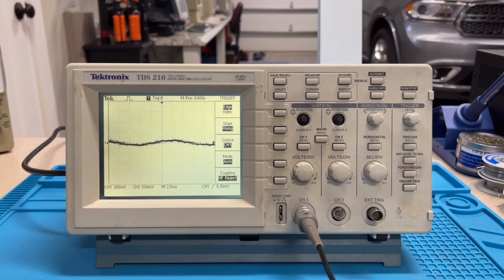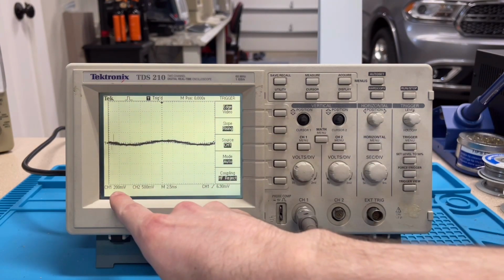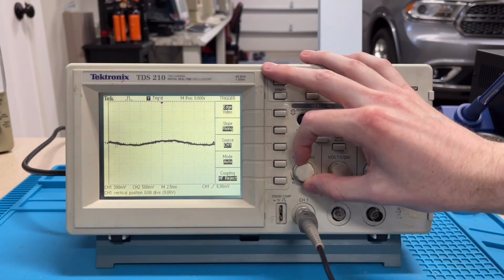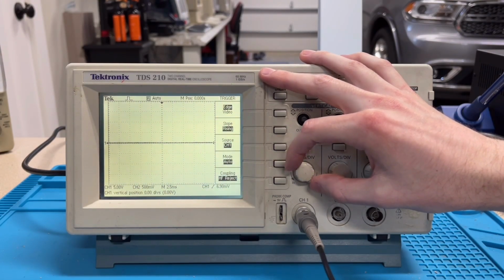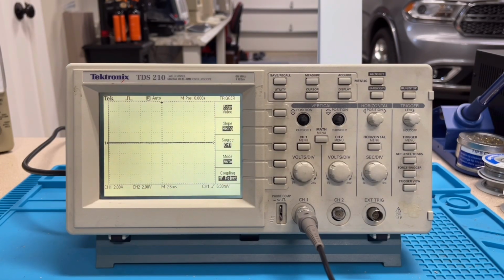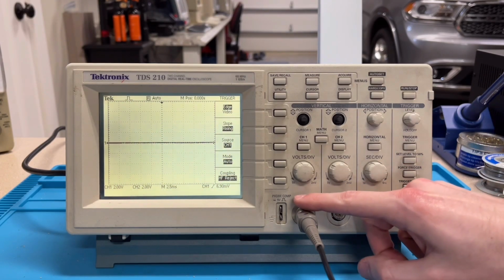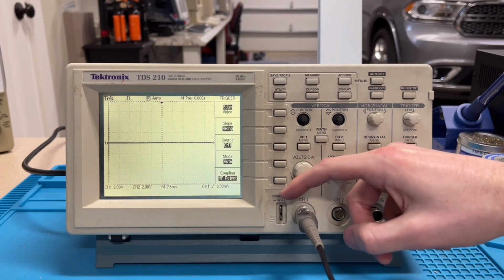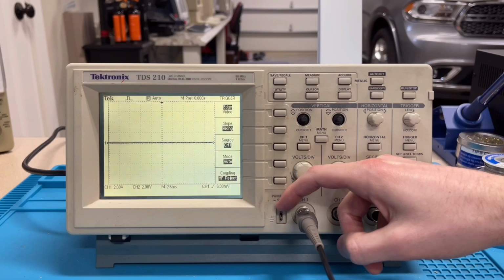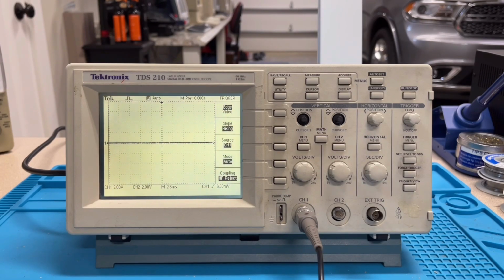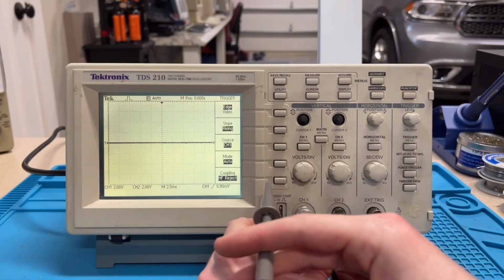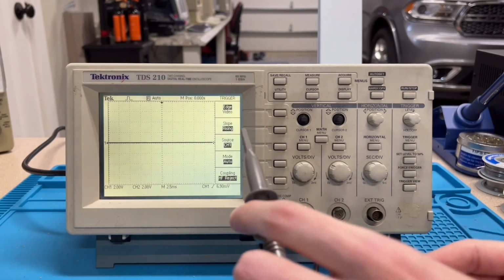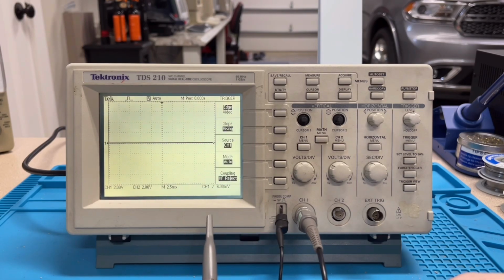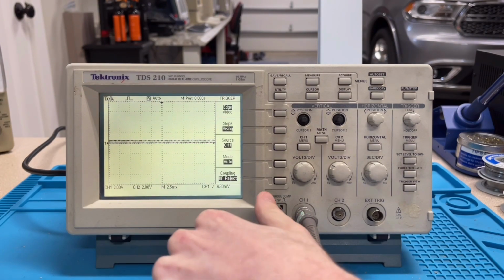And the reason we're getting this noise is because we have the voltage per division at a very low level. We have it at 200 millivolts per division. So if I change this to something like 5 volts, it's not going to show anything. I'll set it for 2 volts per division so I can show you what I'm about to do. On virtually every scope, there will be something called probe compensation. It'll give you a ground and a 5 volt DC hookup right here, and that is so you can calibrate your probes. So we're going to hook the ground up to the bottom connector and then the probe itself to the 5 volt. And what we should see is a 5 volt square wave going across the scope. And you can see we do.